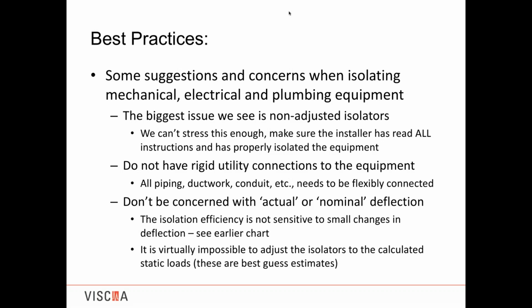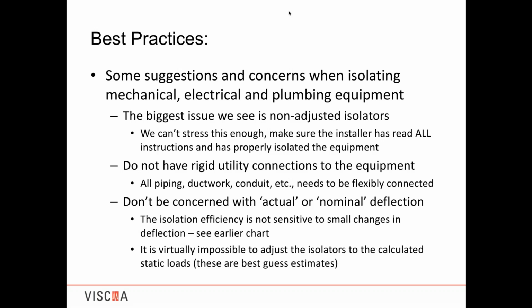And one other thing on here that I don't know if I put before I move on is Angela touched upon the internal isolation. Some of the bigger pieces of equipment have internal fans that are isolated. If you're putting an isolator on the outside of that equipment, you'll need to lock out or put the blocking back in for the internal piece of equipment. Otherwise, you have a spring on a spring and you run into other issues. That happens very often. Rooftop units will have springs underneath the internal fans, but if you're putting them on a 2 or 3 inch deflection curb, that internal fan needs to be locked out.